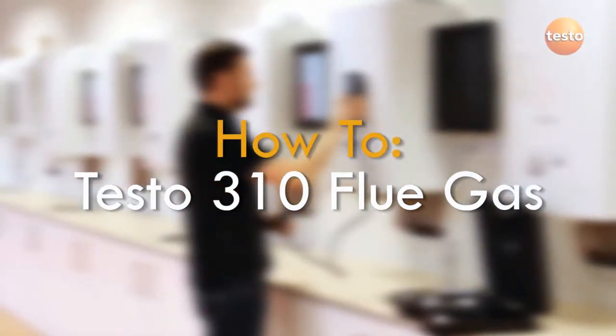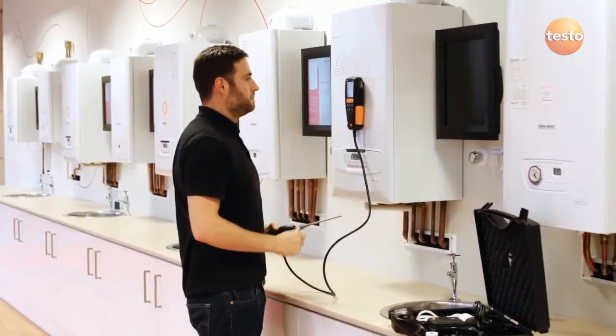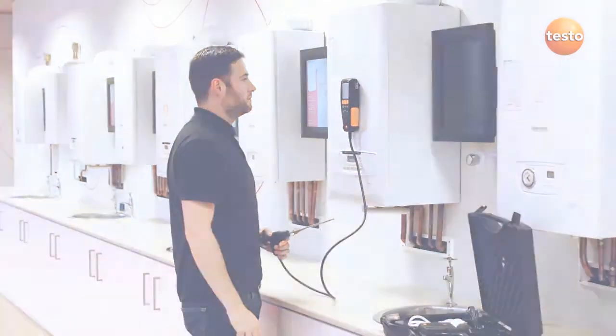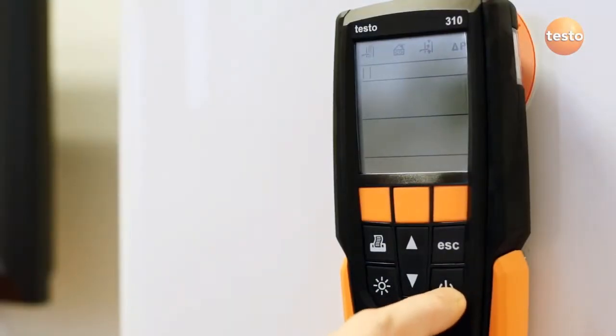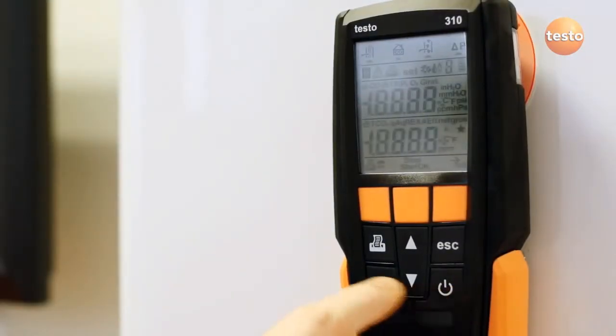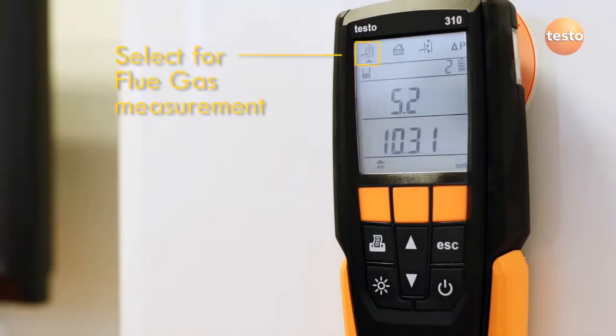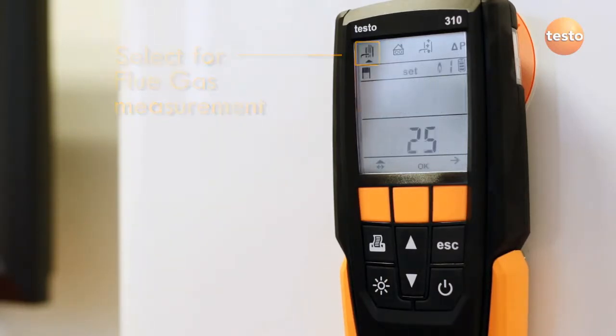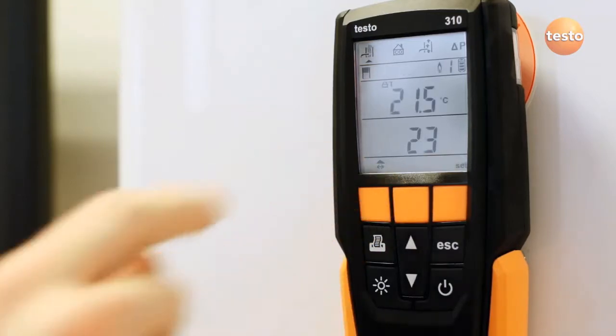The Testo 310 is a flue gas analyzer for use in commissioning and servicing domestic boilers. To carry out a flue gas measurement with the Testo 310, turn the instrument on and make sure the flue gas test icon is selected at the top of the screen. Then let the 310 zero the gas sensors with the probe in fresh air.